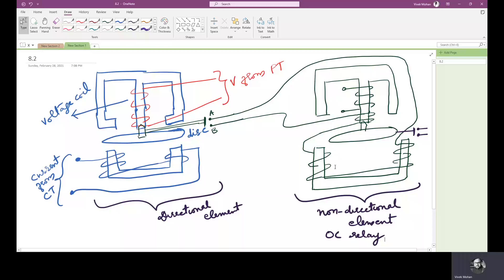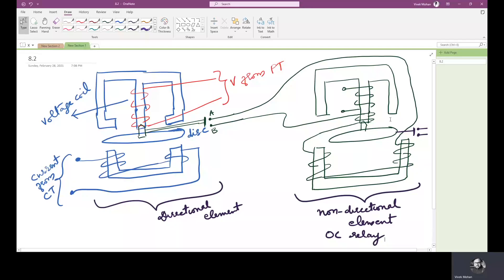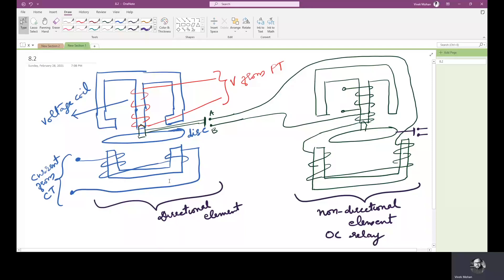The current coil of the directional element is connected in series with the primary winding of the non-directional element. The trip contacts A and B are in series with the winding on the lower magnet of the non-directional element. So unless and until these trip contacts are closed by the movement of the disk of the directional element, the non-directional element will not operate. If the direction is not the desired one, the overcurrent relay will not act and hence the relay will not send a trip signal and the circuit breaker will not isolate the circuit.